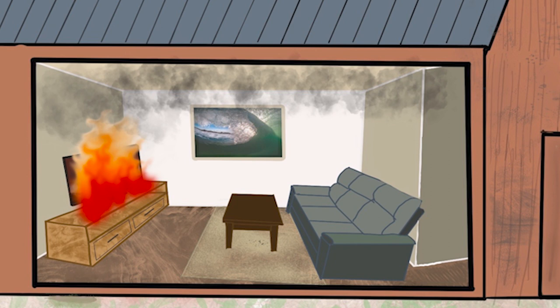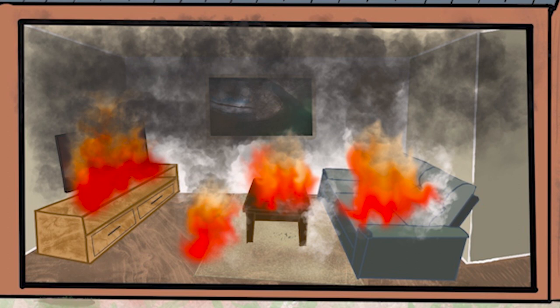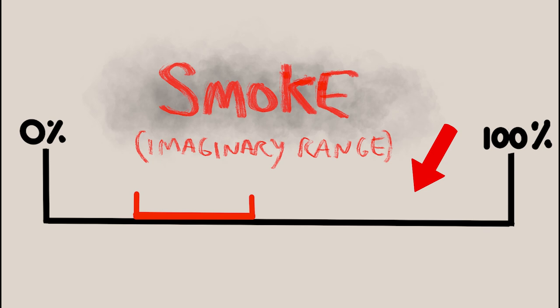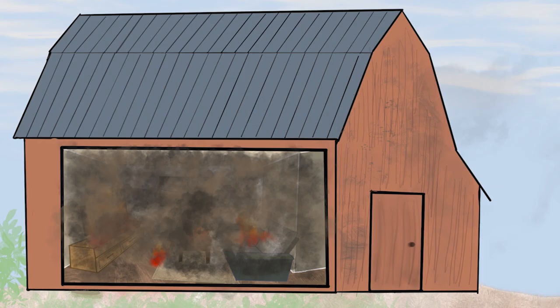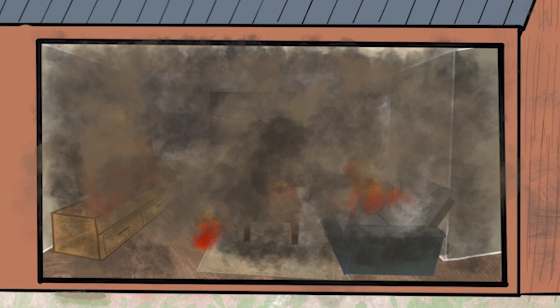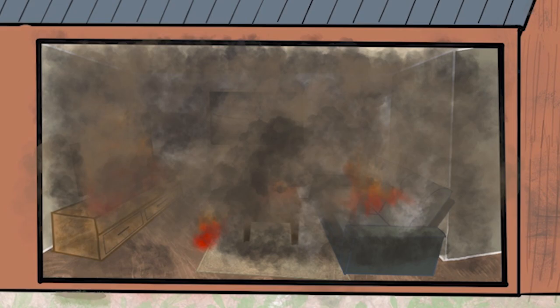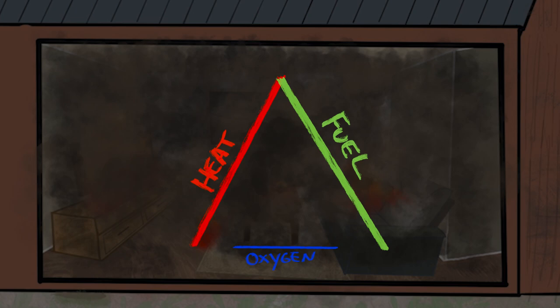As the fuels continue to pyrolyse, more and more flammable gases build up. This means we are going to be well above the upper explosive limit, and therefore it's going to be far too fuel-rich to support combustion. Even after the fire has died down, these gases can continue to build up, because pyrolysis does not need oxygen to occur. The heat remaining from the fire will continue to pyrolyse the fuels and completely fill the room with potentially flammable smoke. Looking at the fire triangle, we have lots of heat and lots of fuel, but nowhere near enough oxygen to support combustion.